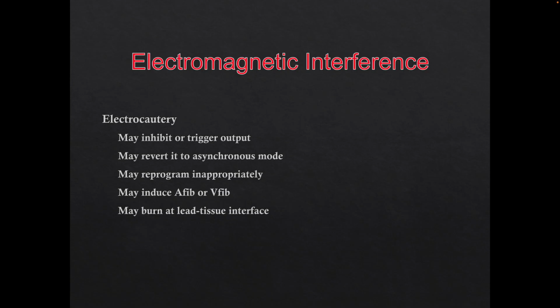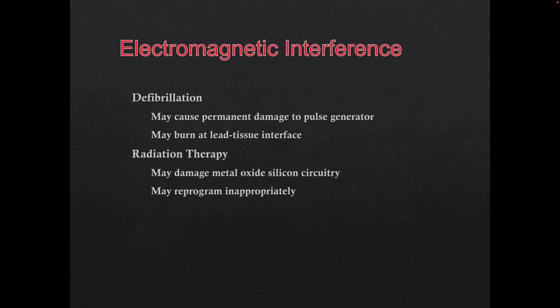And then also, if it heats up the wire, and this is more so with MRIs, it can actually damage tissue. That's why we always want to make sure, I think I have a slide on MRIs, that the wires are MRI conditional when they go for that. Defibrillation may cause permanent damage to the pulse generator, burn tissue, or interfere with the device. And radiation therapy. Defibrillation meaning external defibrillation.